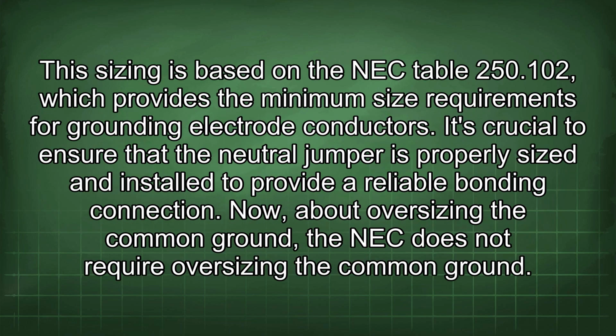This sizing is based on the NEC Table 250.102, which provides the minimum size requirements for grounding electrode conductors. It's crucial to ensure that the neutral jumper is properly sized and installed to provide a reliable bonding connection.